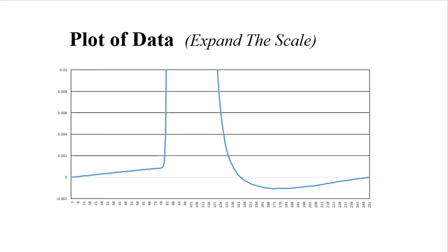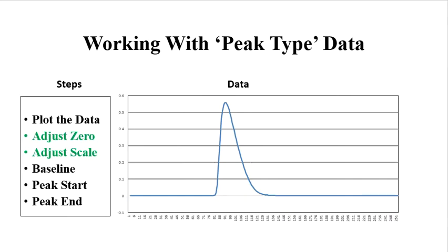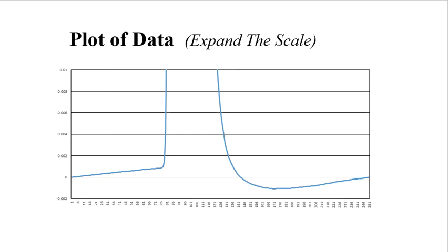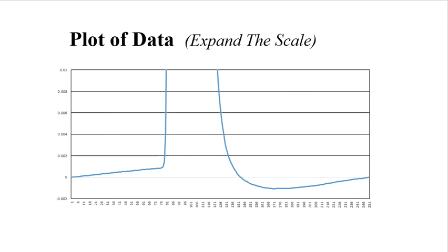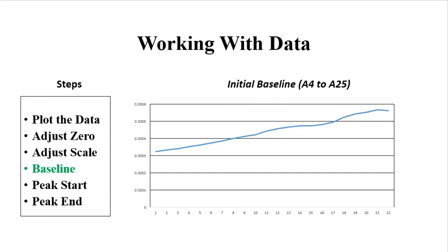Now let's blow up the peak and look for any funny things that are going on. It looks well behaved here, but when you replot it, you'll notice there's a baseline slope and some peculiar artifact on the far side of the peak that you didn't see. That sometimes is caused by chromatography, or by pressure effects in GC, or by a detector that's not properly engineered.